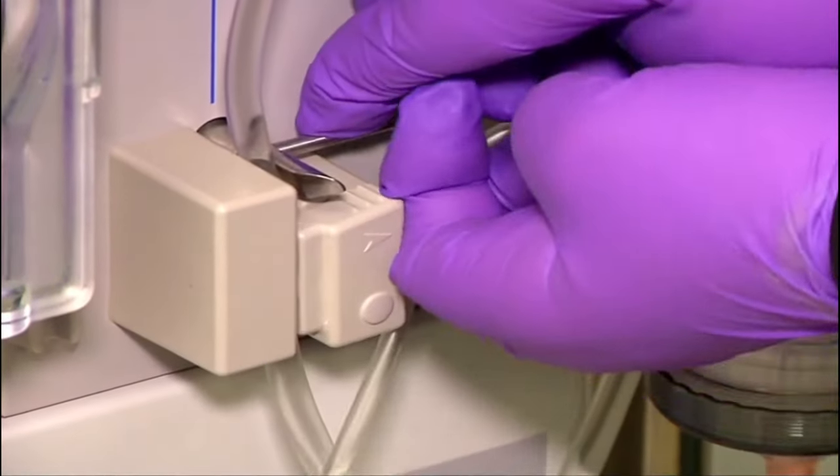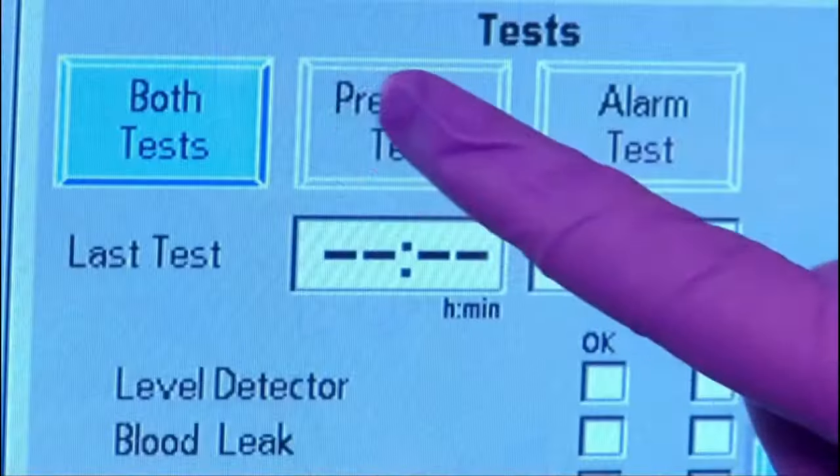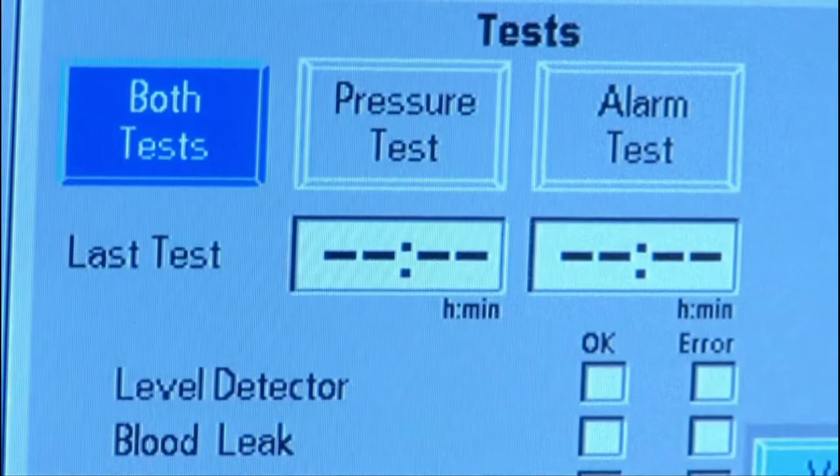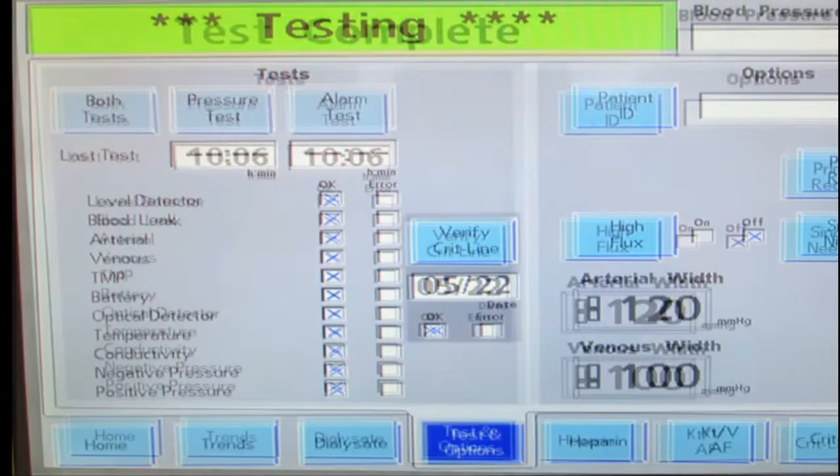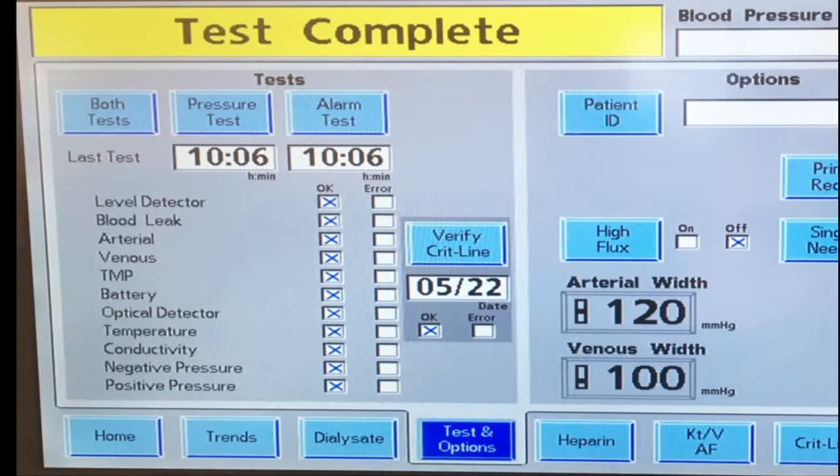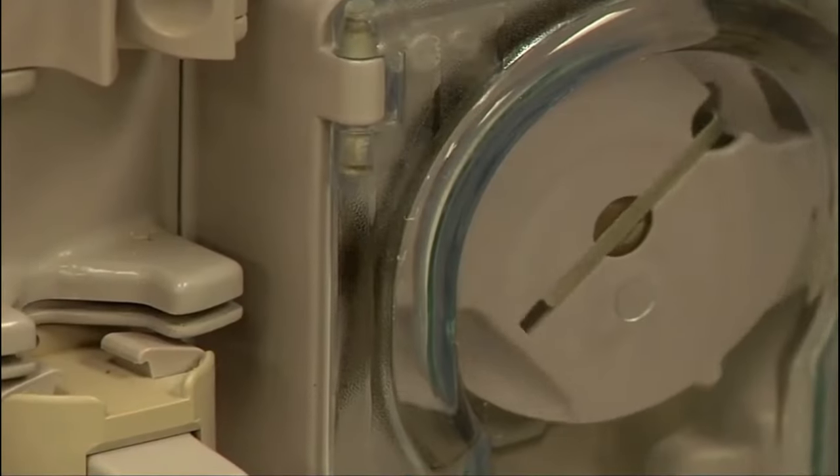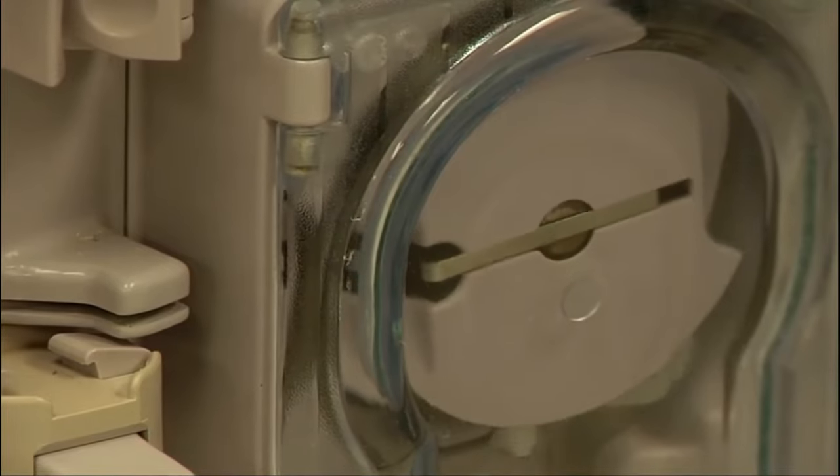Earlier dialysate delivery systems used pressure-controlled filtration, requiring dialysis personnel to calculate the TMP, enter the TMP into the machine, closely monitor the filtration rate, and recalculate and adjust the TMP as needed.